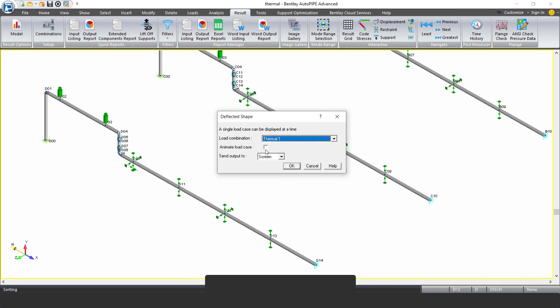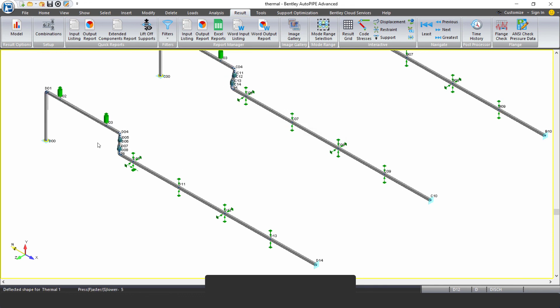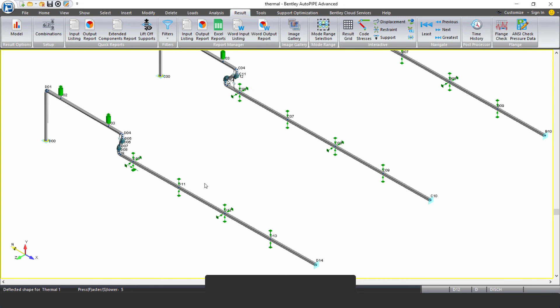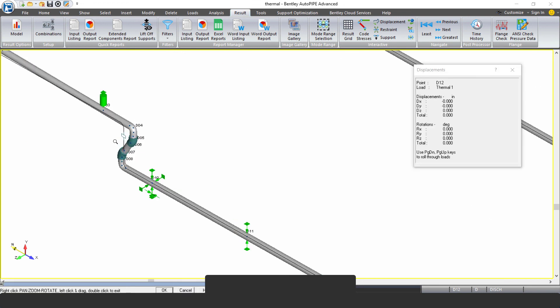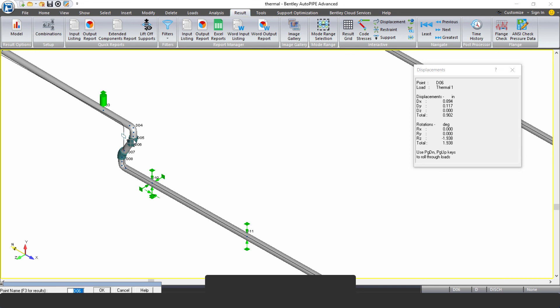So the next thing I want to do is look at my displacement. And if I look at the thermal displacement here, you can just see right away that it's a difference in the animation of how much those expansion joints are bending. And when I stop it and take a look further and look at the actual numbers, I can see that I go from 1.209 to 0.894. So I've now brought it down from an inch of that displacement from the top to the bottom of the expansion joint to about 0.3 inches. So I brought it down quite a lot and have much of a better chance of satisfying the design displacement criteria of the expansion joint itself.